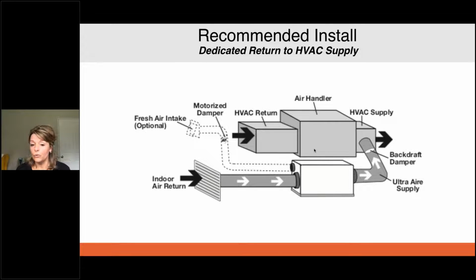You can use the dehumidifier for fresh air ventilation. They all have a duct for fresh air, except for our smallest unit, a 70 pint unit. Then we tie into the HVAC supply. Installing it this way is the most energy efficient, because we don't have to use the HVAC fan when the dehumidifier is running.